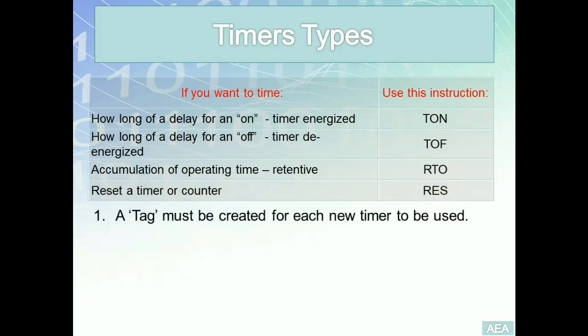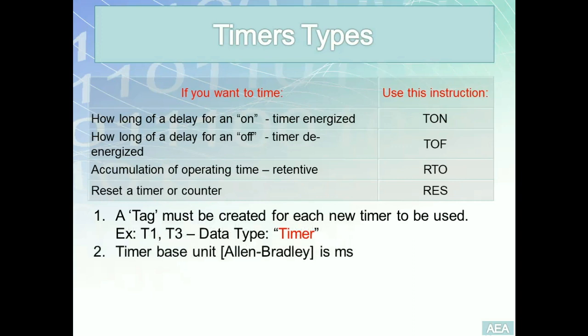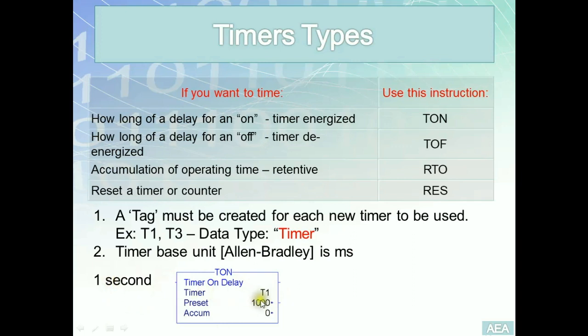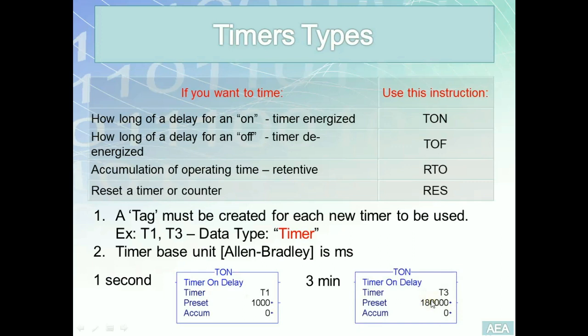Two main factors to remember when creating a timer: first, a tag must be created for each timer used in the program — you can give it any name, but the data type must be timer. Second, the base unit in Allen Bradley is a millisecond, so if you want the timer to run for one second, the preset value must be 1,000. For three minutes, the preset value would be 180,000 milliseconds.